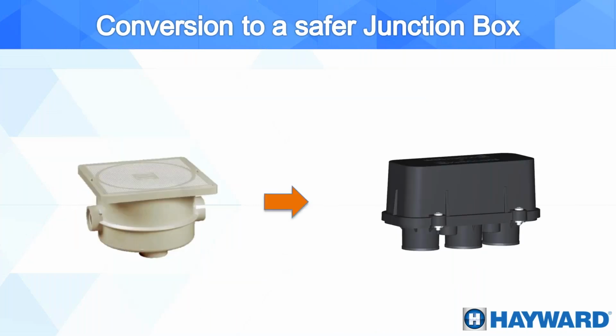As a safety recommendation and as a better installation, also keep in mind that many times in our markets we are using these junction boxes, which are flat and fit right next to the pool. They are not necessarily the best junction boxes that we should be using. It is important to keep that in mind, because this junction box doesn't give us the safety that we need. It doesn't give us the distances that we need in order to do a proper and safe installation.